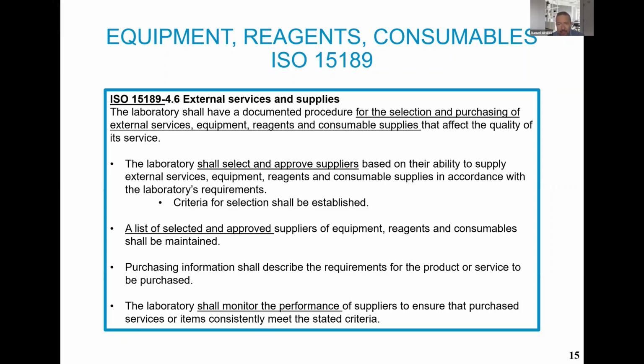And how do we do that? We want to make sure that those reagents and that equipment is validated, is verified before we put into place. So we can have a separate conversation about that topic, but there is a lot that we need to ensure before we use those reagents. We need to ensure that those reagents meet the performance claims that the manufacturer will say on their package insert. And how do we do that? Doing validation studies, we run precision, accuracy, carryover, and so on.